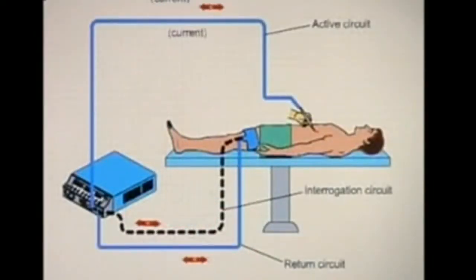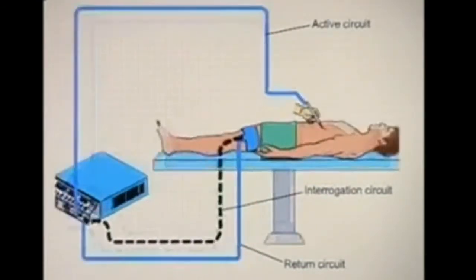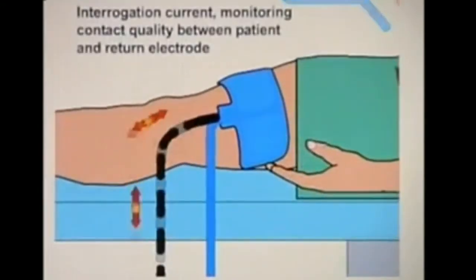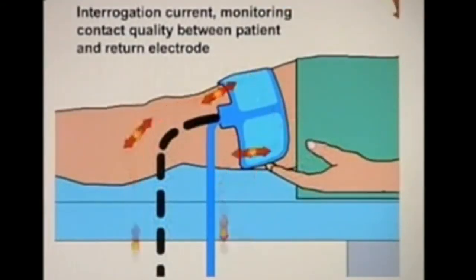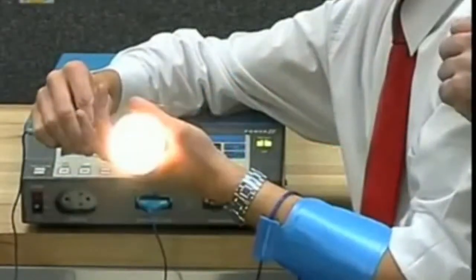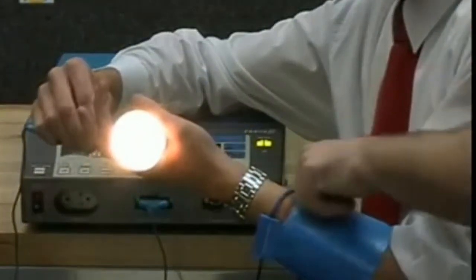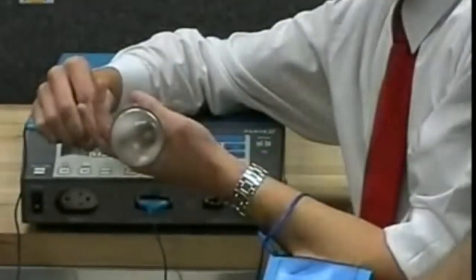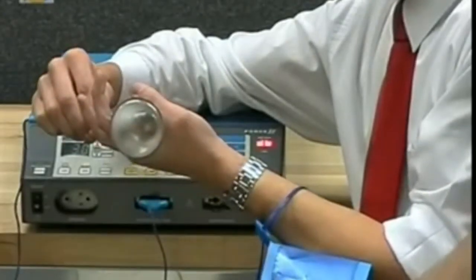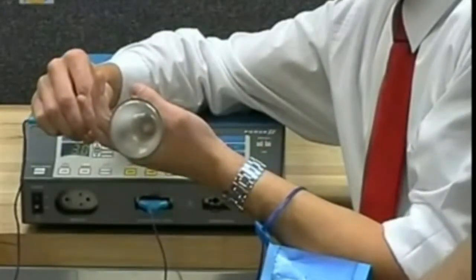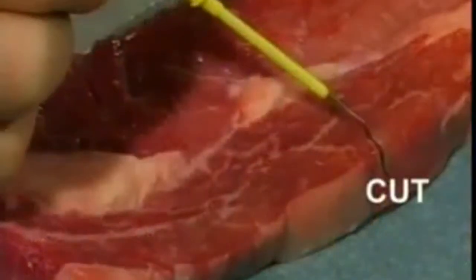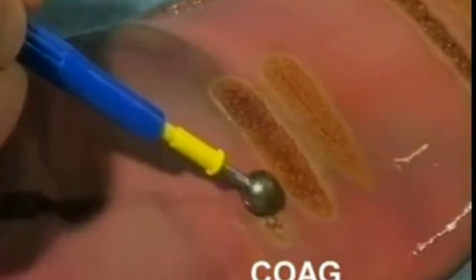This is another safety feature, whereby the electrosurgical generator constantly checks how well the patient return electrode is applied by measuring impedance across the pad. Should the pad begin to peel off the skin, the impedance rises and the output from the generator shuts down until the patient return electrode is properly reapplied. What modes of electrosurgery are you aware of? Let's look at the two common modes: cut and coagulation.